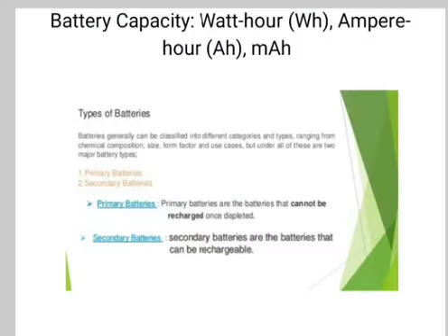The battery capacity represents the maximum amount of energy that can be extracted from the battery under certain specified conditions. However, the actual energy storage capability of the battery can vary significantly from the nominal rated capacity, as the battery capacity depends strongly on the age and past history of the battery, the charging or discharging of the battery, and the temperature. Now, the units of battery capacity.